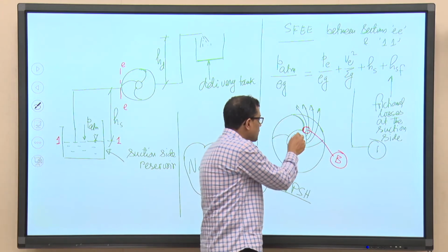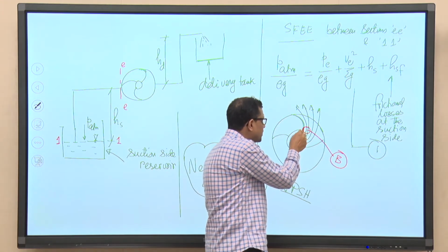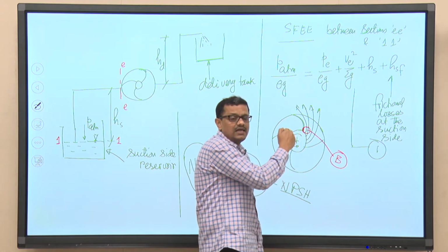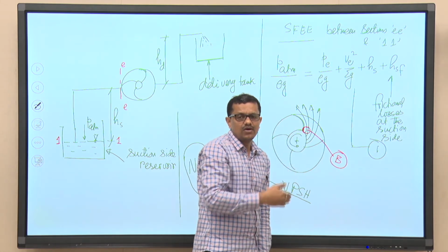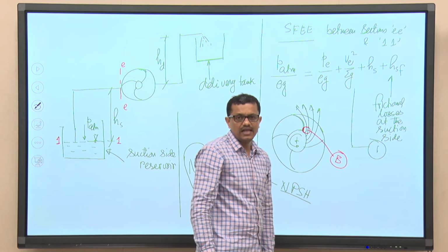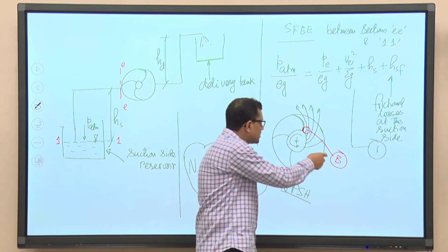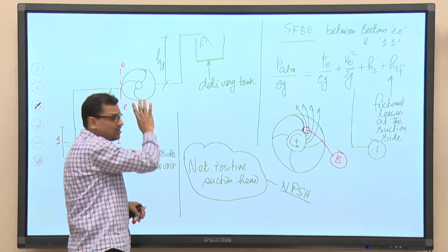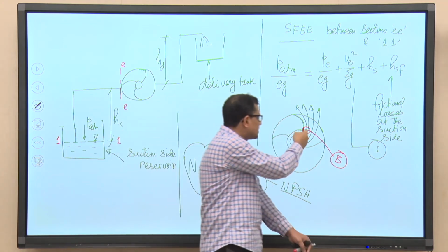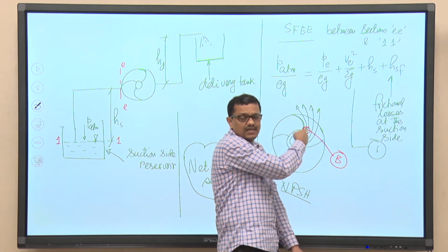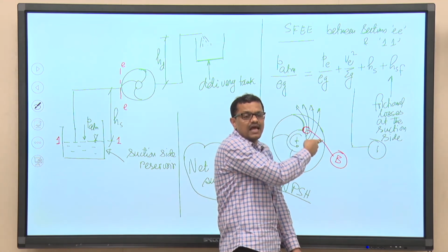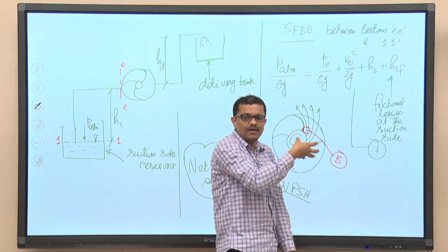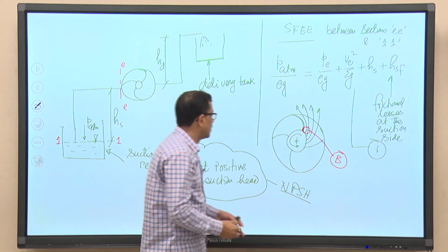So, when liquid is approaching just slightly inside the leading edge of the pump vane at the inlet, this point B, which is very close to section E, the liquid will accelerate and flow velocity will be high. At that place pressure will fall and static pressure may become below the vapor pressure. So, cavitation will occur.